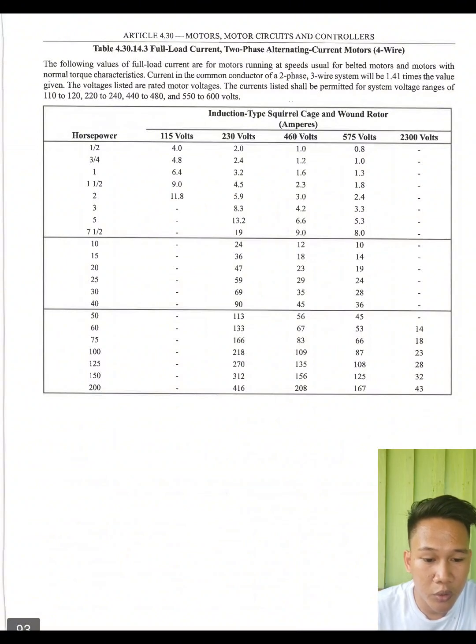So, next is table 4.30.14.3, full load current, two-phase alternating current motors, 4-wire. So, the following values of full load current are for motors running at speeds usual for belted motors and motors with normal torque characteristics. Current in the common conductor of a two-phase 3-wire system will be 1.41 times the value given. The voltages listed are rated motor voltages. The current listed shall be permitted for system voltage ranges of 110 to 120, 220 to 240, 440 to 480, and 550 to 600 volts.